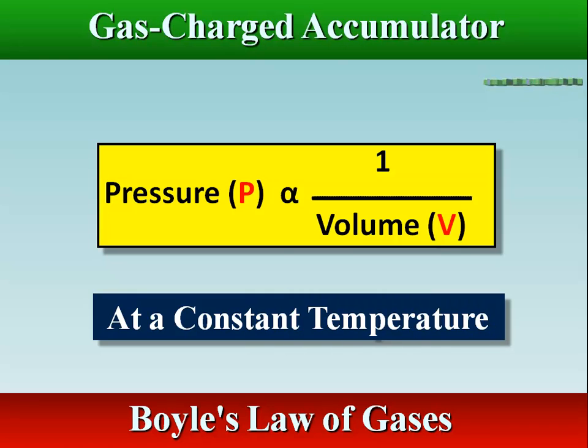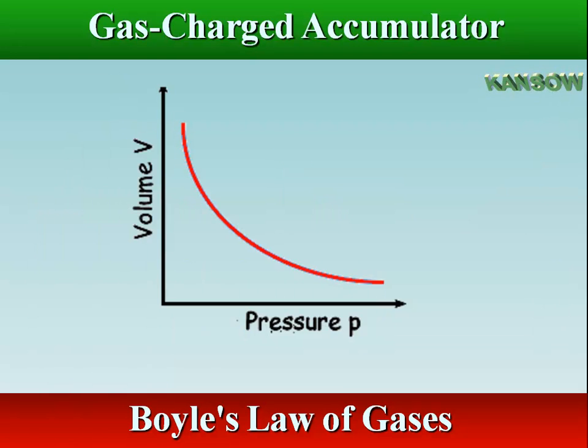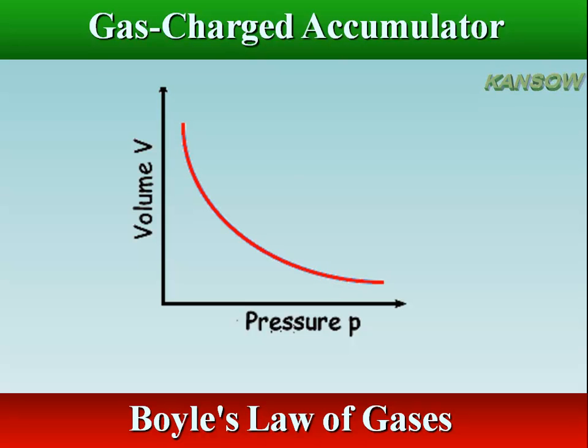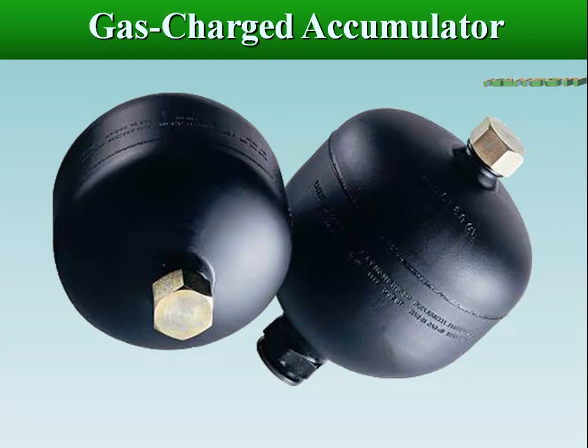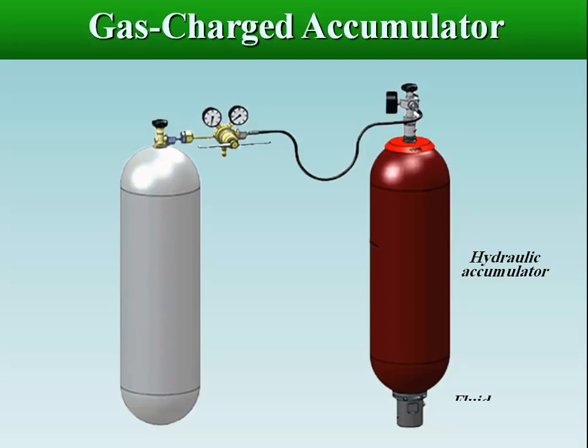The gas-loaded type hydraulic accumulator operates in accordance with Boyle's Law of Gases, according to which the pressure of a gas varies inversely with its volume for a constant temperature process. It is popularly known as a hydropneumatic accumulator. It applies force to the liquid by using a compressed gas that acts as the spring. It uses inert gas, nitrogen, under pressure that provides the compressive force on fluid.